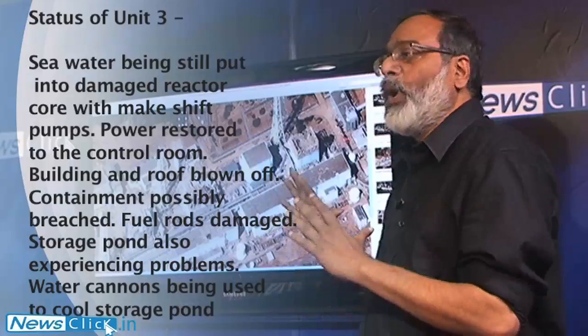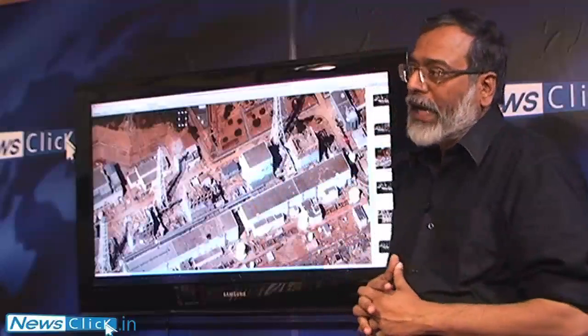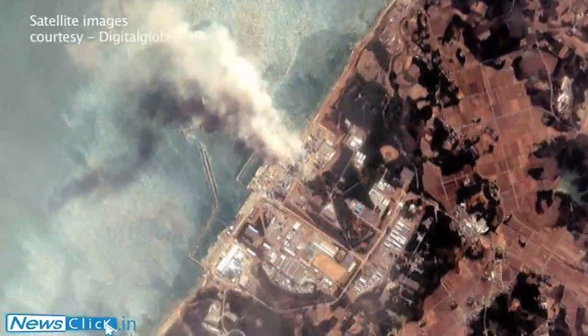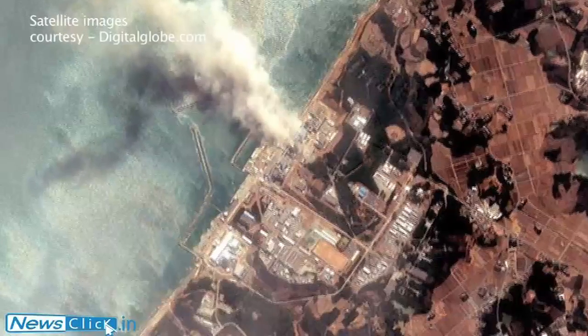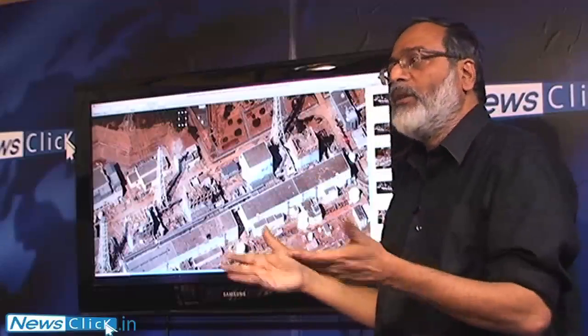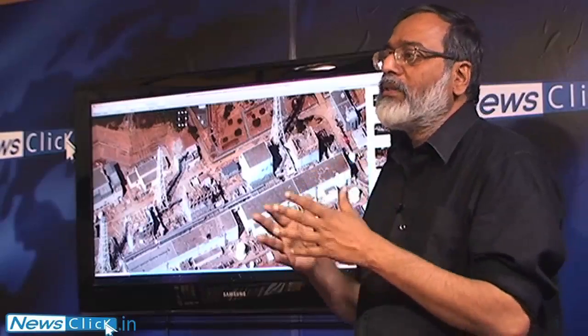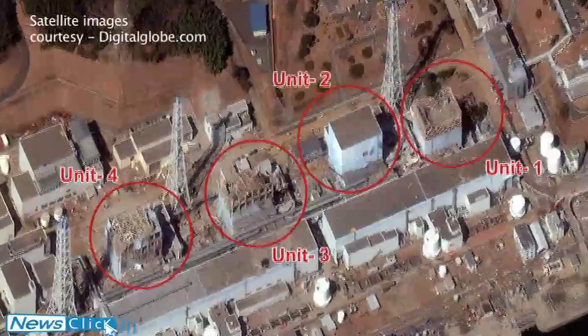So we have a situation where we effectively still have a crisis in these four reactors. Storage ponds — two of them are still in trouble. The cooling systems are still not working for any of them. There is some control, but it is really with a completely makeshift arrangement — fire water pumps, water cannons, seawater and boron being pumped into the reactors. The situation still is very much on the edge, but it is not heading towards a meltdown as was feared earlier.